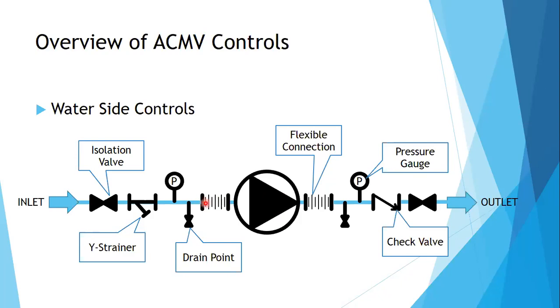Just like before, you also have your flexible connectors. So this pump, since it's running, it's vibrating. We don't want this vibration to transfer to your rigid pipes. That's why you put your flexible connectors. Since we're dealing with same inlet temperature and same outlet temperature, there's no change in temperature within the pumps. We don't put the temperature gauge anymore. We only put the pressure gauge to know the inlet pressure and outlet pressure of the pump so that you can verify if the pump is running as per desired.